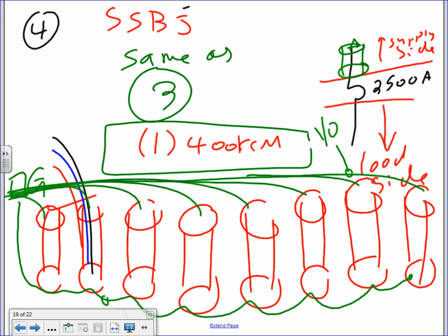Can you guys see right in here? So that will be one conductor, 400 kcm. Everybody can see that? One conductor, 400 kcm. Loop them all together, daisy chain them from 1 to 2 to 3 all the way to 8 and to the ground bar. That conductor will be 400 kcm.